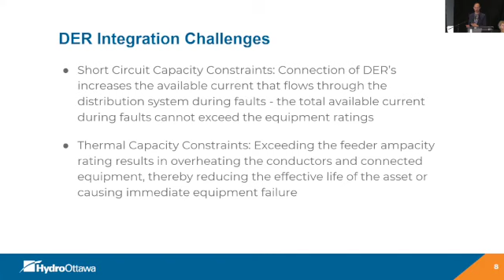Each of these, there are ways to address them. From the short circuit capacity perspective, we have everything from opening our tie breakers at our stations to installing bus tie reactors. There's fast switching schemes with new technology that we can apply. For thermal limits, we can do load transfers and upgrade the conductor equipment. To Brian's point, all of this costs dollars. All of this requires coordination, and especially with a higher penetration and the transition to more DERs on the system, we need to have that visibility into where to make those investments.